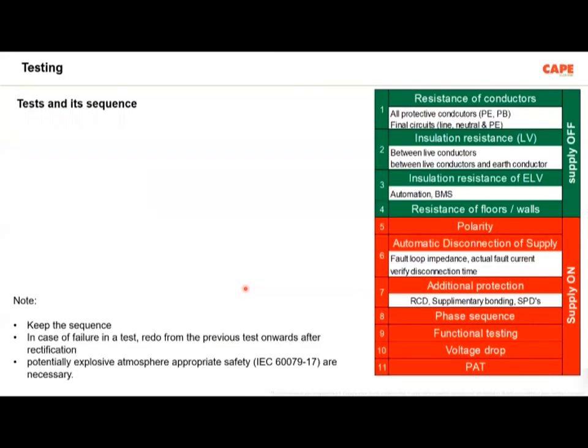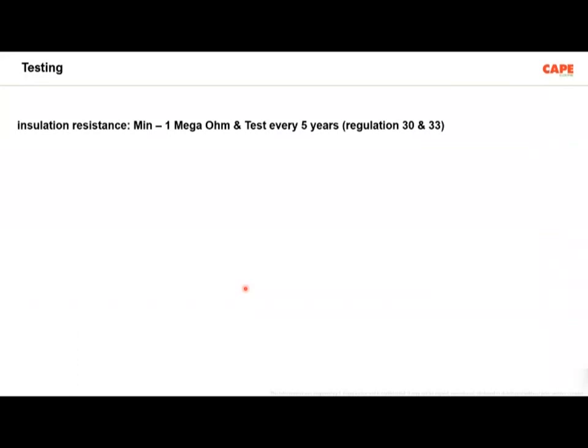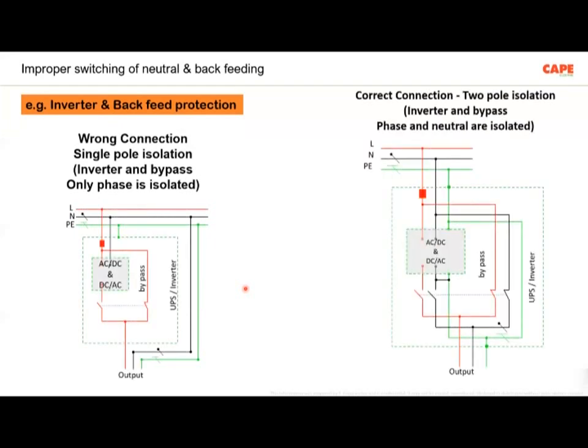Now, with the coordination of the testing and the inspection, which is as per the upcoming National Electrical Code as well as the guide, we will have more clarity on this particular subject. With respect to insulation resistance, as I said, regulation number 33 is very clearly mentioned. Minimum 1 mega ohm within your electrical installation between current carrying conductors, that means phase and neutral, to earth. Minimum 1 mega ohm. But we always use devices which violate this requirement.